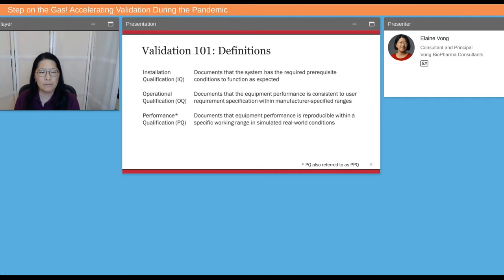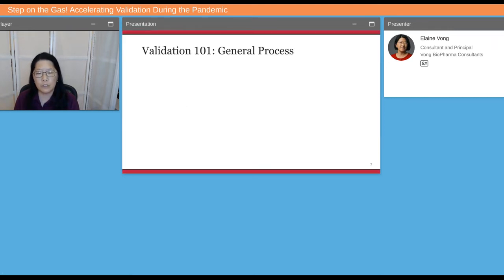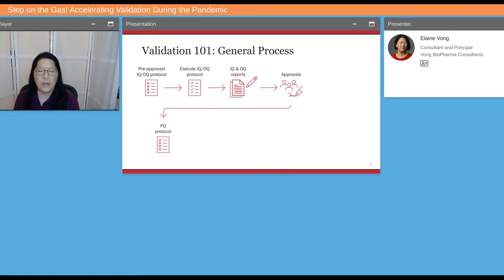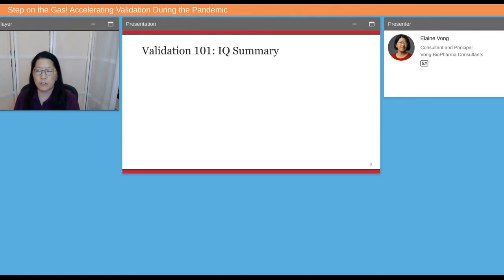And performance qualification documents that equipment performance is reproducible within the specific working range in simulated real-world conditions. So the general process for validating is someone pre-approves an IQ-OQ protocol, executes that protocol, writes their report for the IQ-OQ, and gets their approvals. Then it goes on to PQ if there's one required. You need a pre-approved protocol, execute that protocol, write your report, and gain approvals for those as well. Finally, you're complete. Along the way, there's a handling of lots of paper, unless your company is one of the ones that we'll talk about later.